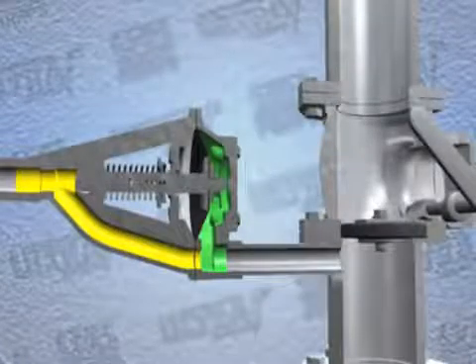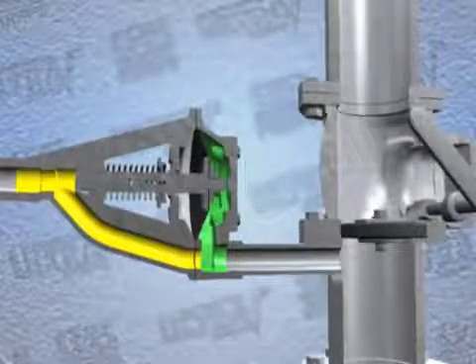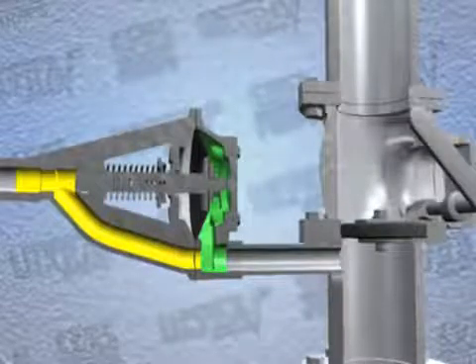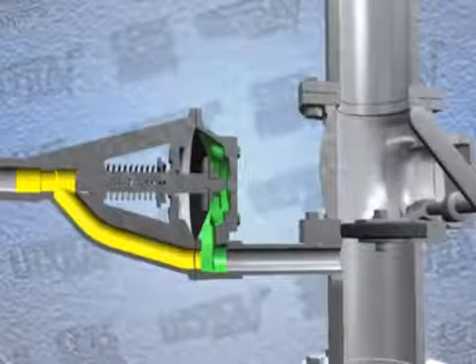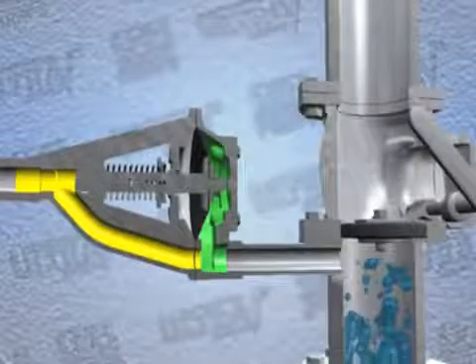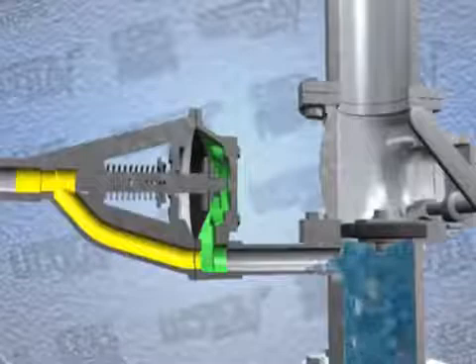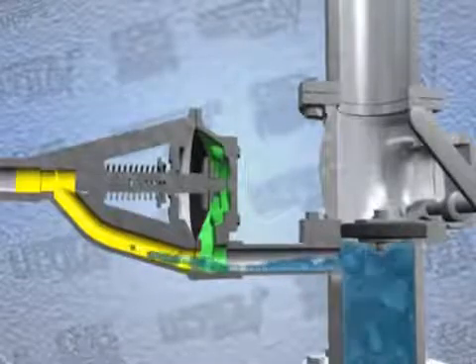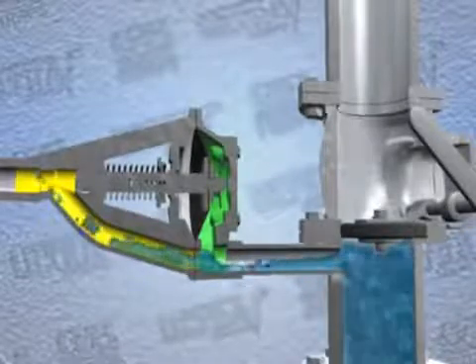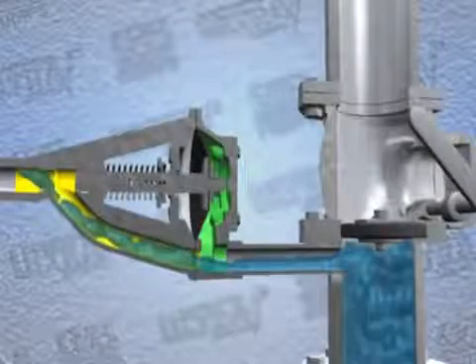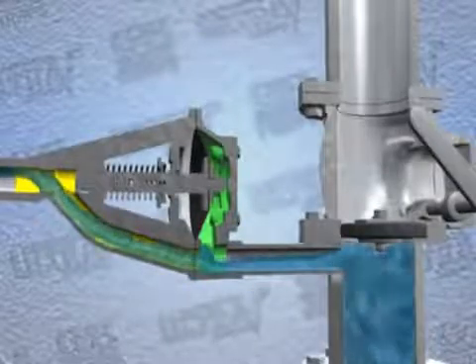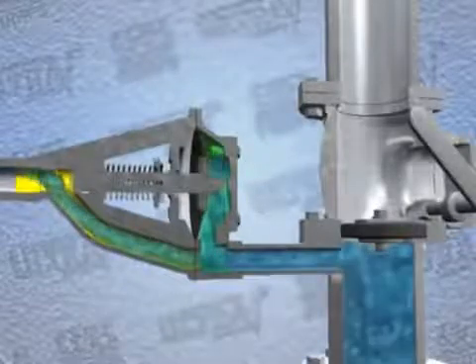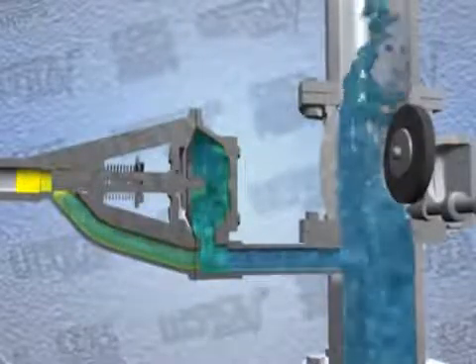An air release valve and discharge valve may be required if a pump is operating against substantial static discharge head. The air release valve is installed between the pump discharge outlet and a check valve in the discharge piping. During the priming or re-priming process, this valve allows any air in the pump and suction line to be vented and returned back to the sump. As the liquid rises in the discharge line, it fills the back side of the valve. The pump builds pressure and causes the air release valve to close, shutting off the passage on the discharge side of the valve.